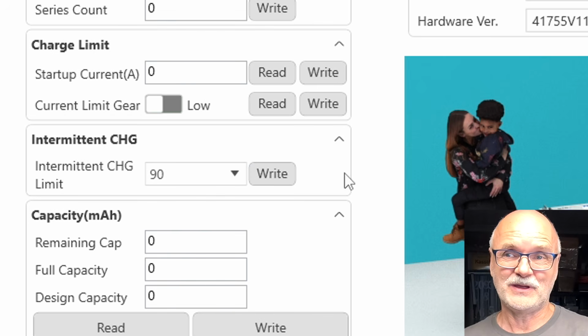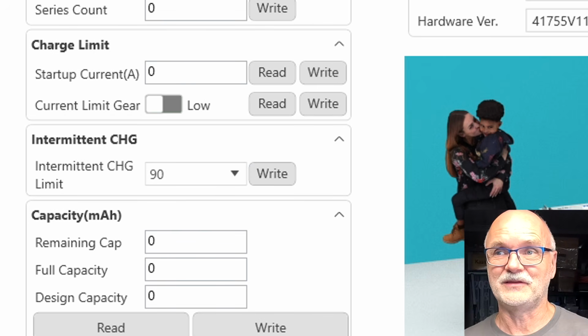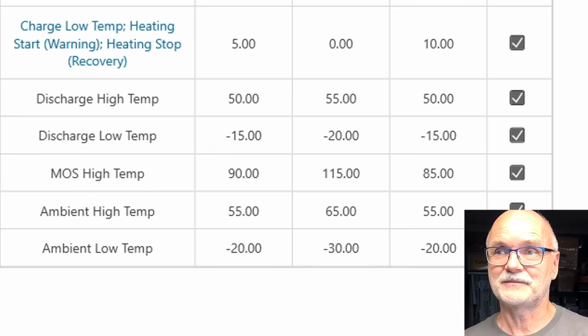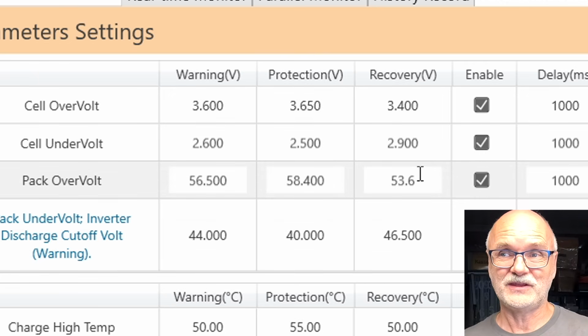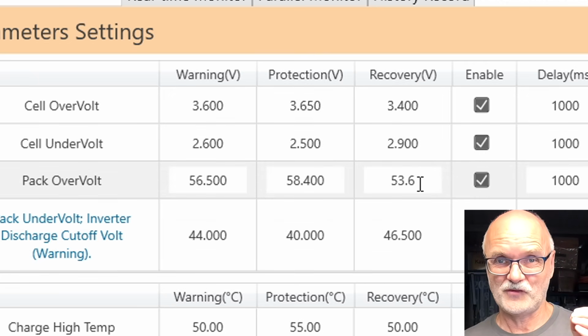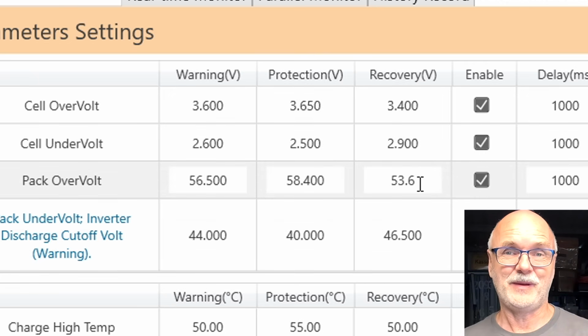So 90% is set as the Intermittent CHG limit. Going back to the parameters, it would now stay on 53.6 volts float voltage until the battery goes under 90% state of charge.